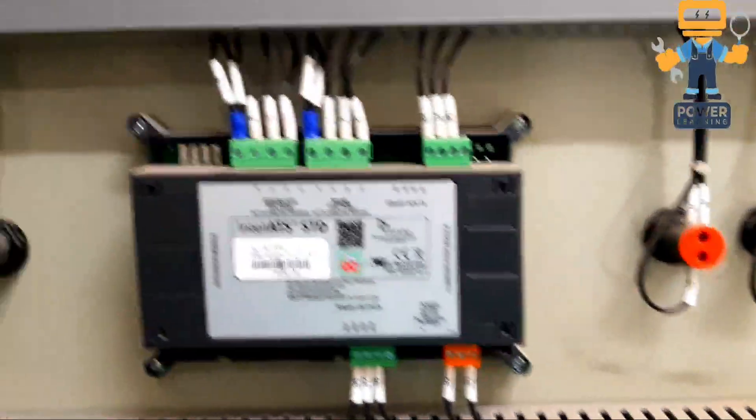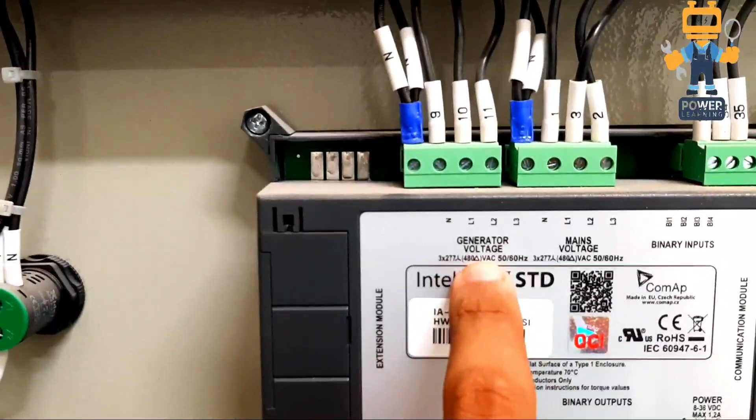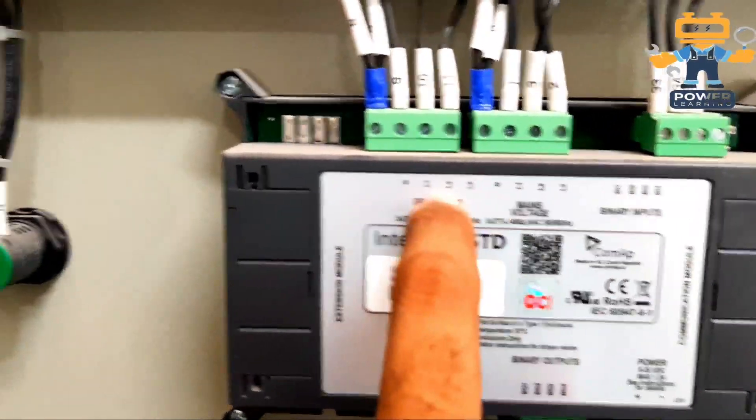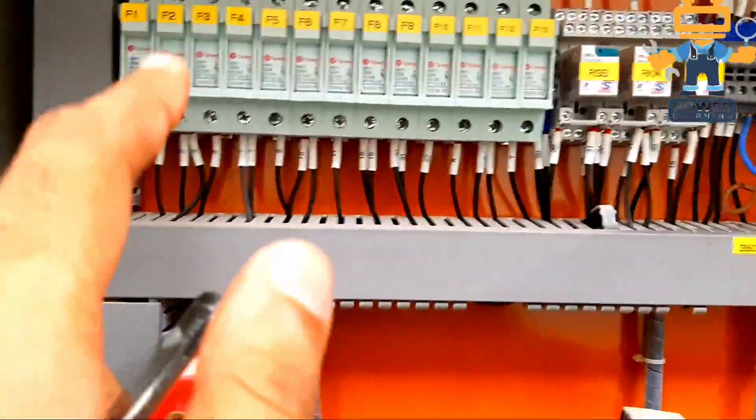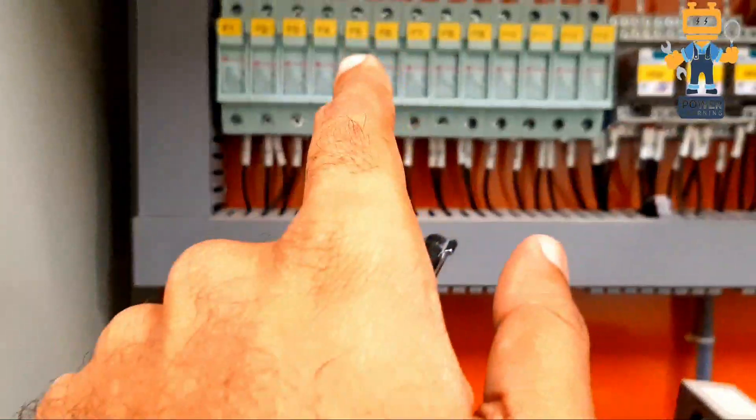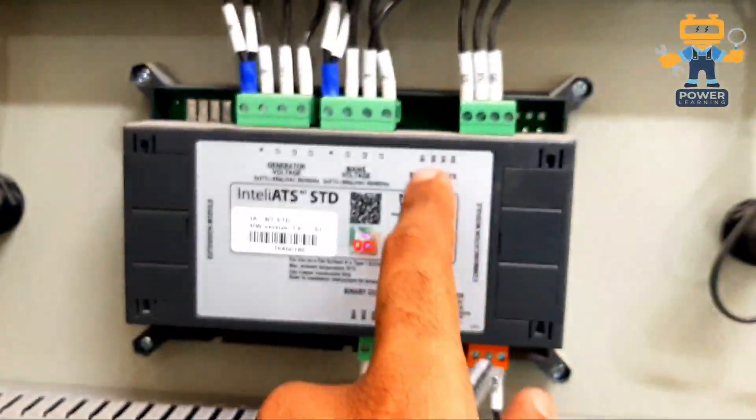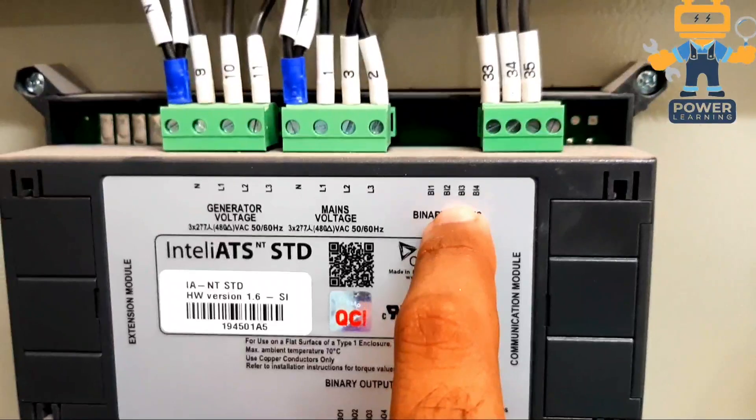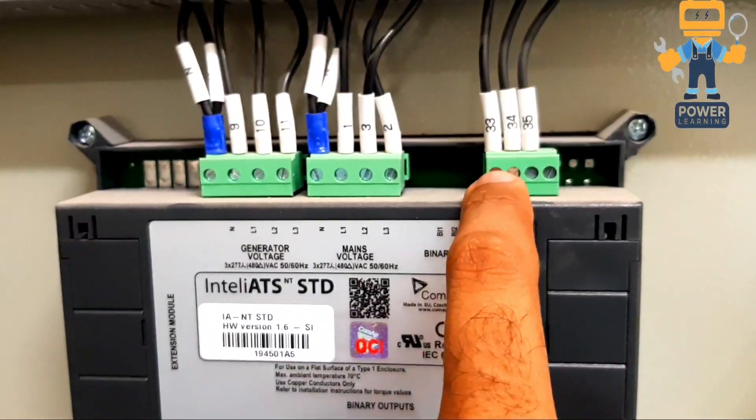First we have generator voltage: neutral, line one, line two, line three, which is coming from these three fuses. After that, mains voltage, which is also coming from these three fuses. These are the binary inputs, digital inputs for signaling. Once the breaker is closed, it will show us breaker is closed. These two are for breaker close and the third binary input is for remote signal on and off.